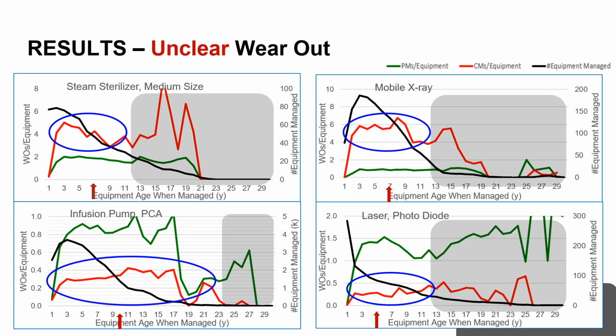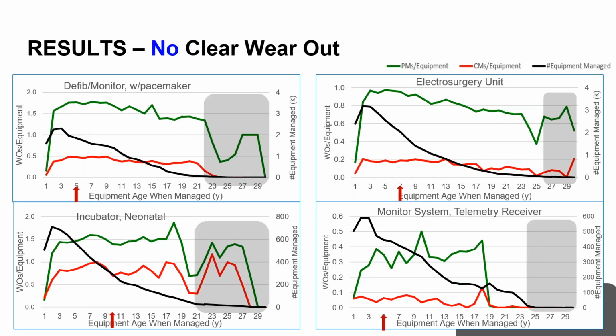Okay, there are some that we say unclear because the numbers are not very clear, and it's not exactly rising or coming down or flat. So we say, okay, these ones we need more data to understand a little better what's going on here. But there are ones that we really claim that there is no wear out of any type that we can see. For example, defibrillators, very flat, and up to something like 20 years. We see defibrillators being used up to 20 years, although AHA says you need to replace every 5 years.